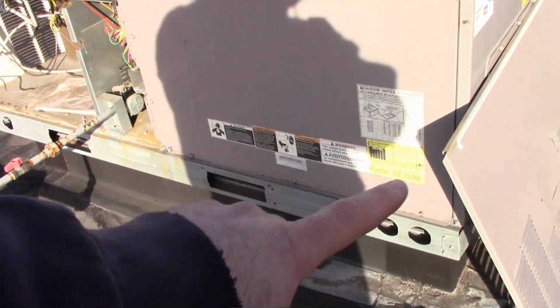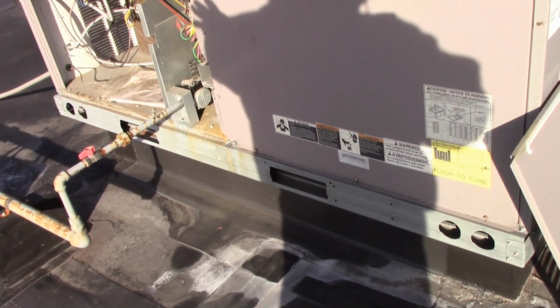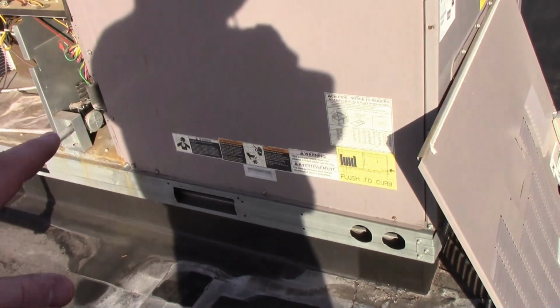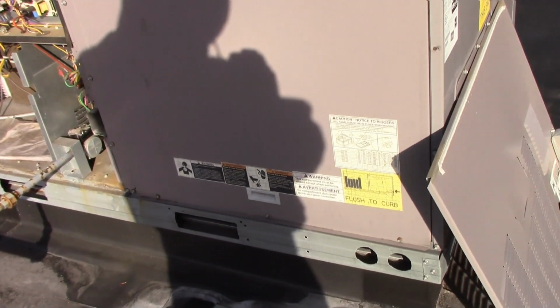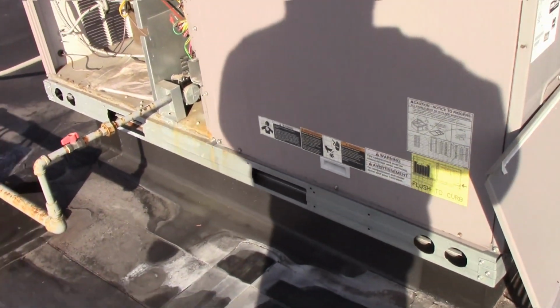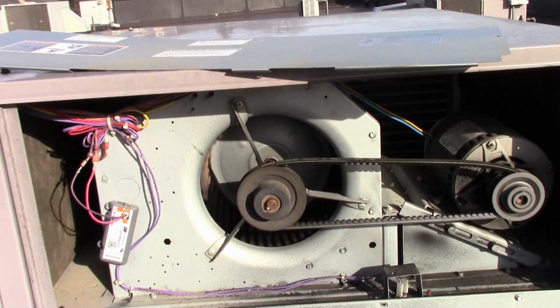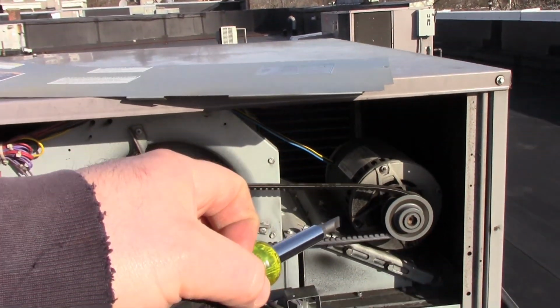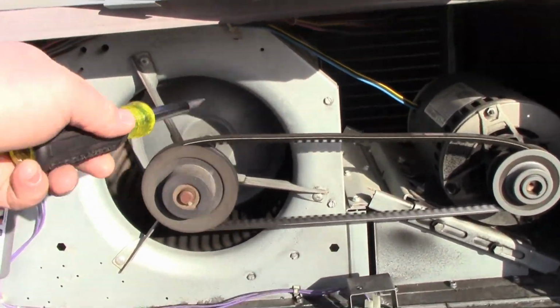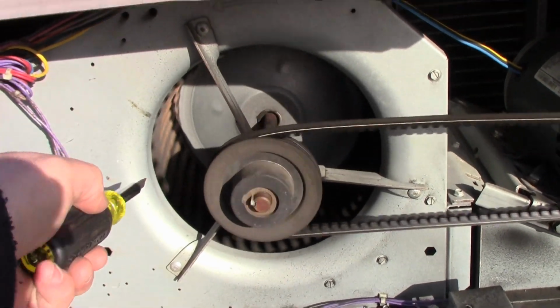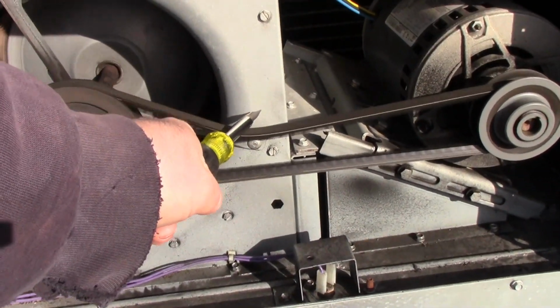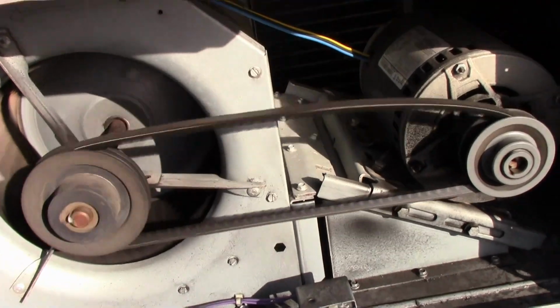So first thing, I'm going to take this panel off. I'm not going to reset the unit. I'm going to check the motor, the belt, and then we'll check the filters, and then we'll check the limit switch. Okay, so motor's good, belt is loose, blower's going pretty slow. Should be somewhere in that range of speed.